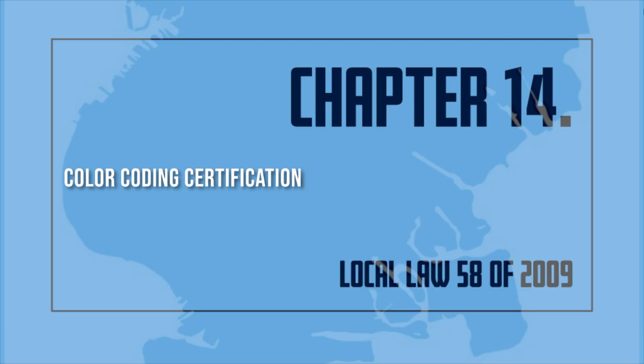Color coding certification. Buildings under construction: the special inspector will confirm compliance before the walls are enclosed. Existing buildings: owners of buildings with exposed sprinkler piping and standpipes must comply and hire one of 4 types of contractors to certify the color coding. These are licensed master plumbers, licensed master fire suppression piping contractors, registered design professionals, or people with the appropriate Fire Department certificate of fitness.